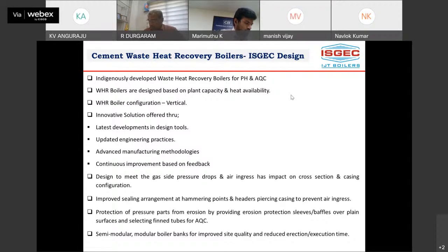Mostly the boilers are vertical in configuration. While making the design, like we mentioned, with the latest development in design tools, without CFD no boiler is designed. That means we do the CFD analysis for all boilers, the PH or AQC, because it's very much essential, especially in AQC. The velocity plays a very important role, also the gas distribution, because the dust is very erosive in nature. So definitely the CFD analysis is done. Also the duct configuration, everything, is done in the CFD analysis.